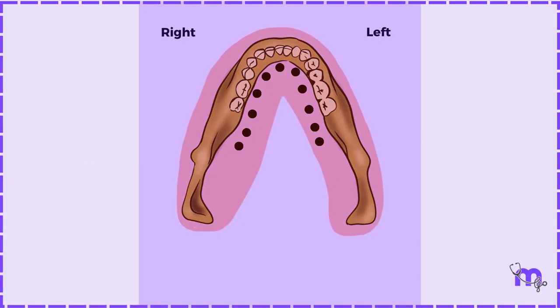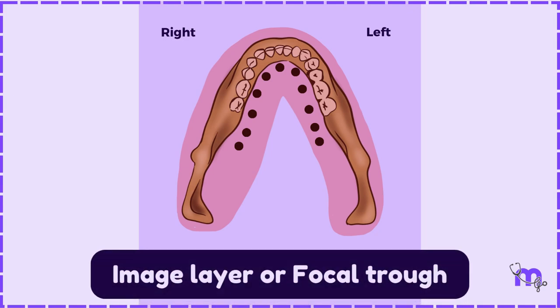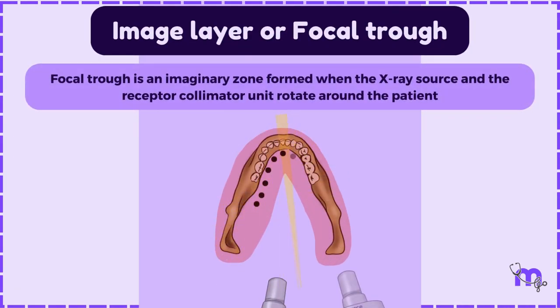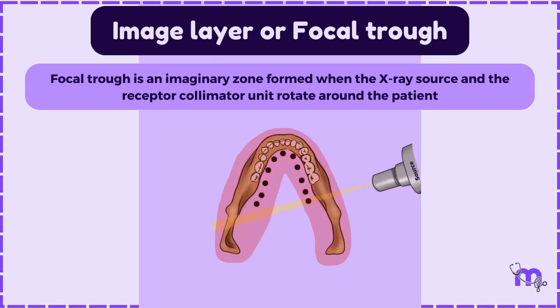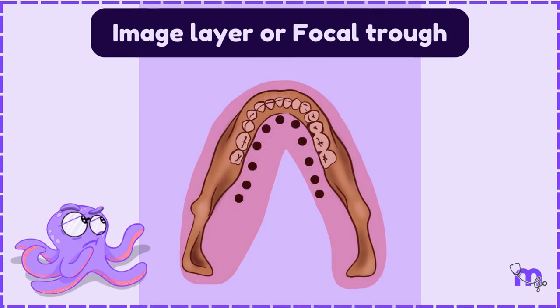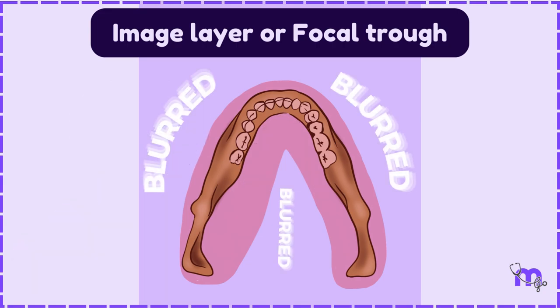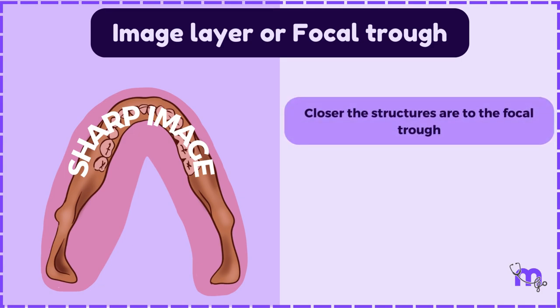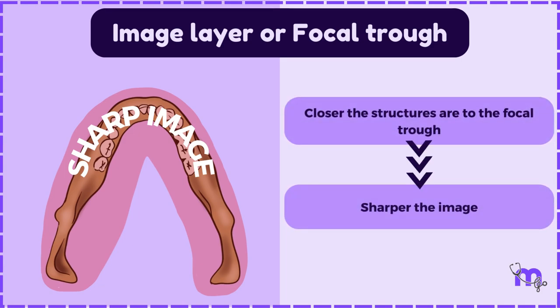The area through which the X-rays pass to create the required image is called the image layer or the focal trough. The focal trough is an imaginary zone formed when the X-ray source and the receptor-collimator unit rotate around the patient. All the structures within the focal trough are clearly obtained. Therefore, the closer the structures are to the focal trough, the sharper they appear.